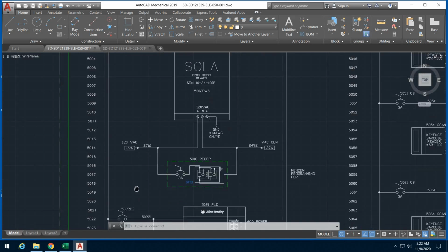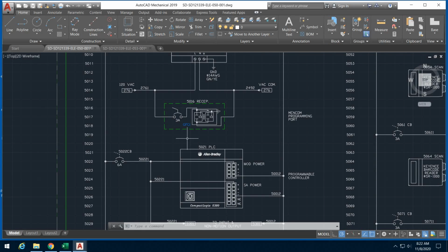But if there was a safety relay right in here, and there's an outputted 24 volts from it, that would get labeled in this area over here as like hazardous motion or hazardous output power, and then it would get used to control, probably in our case, PLC output cards would be given power when that is made, or when that particular power is on, so that if a safety gate or a light screen or an e-stop is pressed, that loses power, and then all the hazardous outputs are killed, let's say.